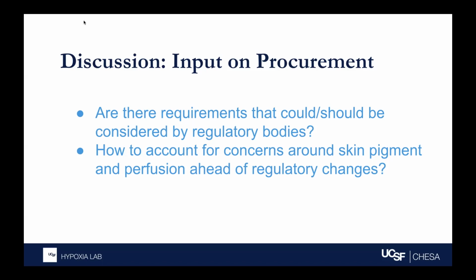And in this case, that ISO standard is a harmonized standard. Therefore, if you conform with that standard, if you meet that standard, you can assume that you conform with the European regulation. But I think the bit that's different is that, particularly in the UK, we don't just rely on the regulation to decide what's available in the National Health Service.